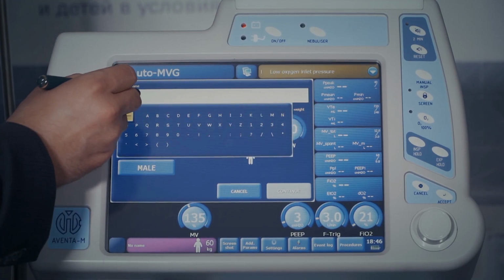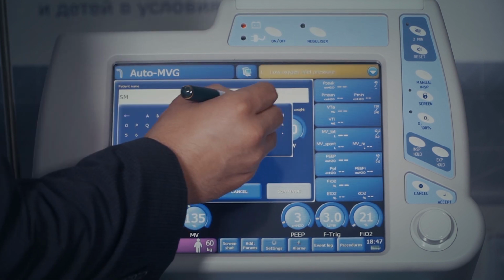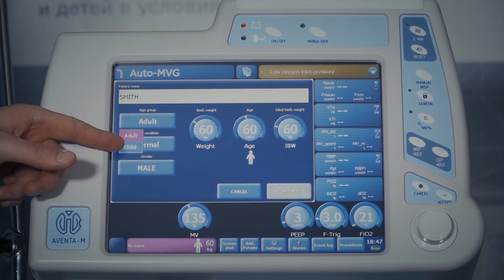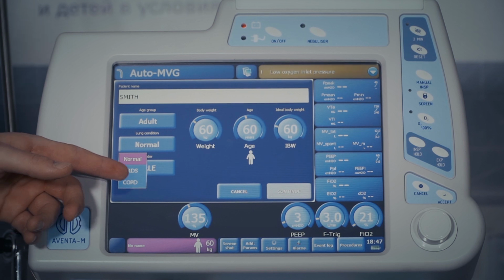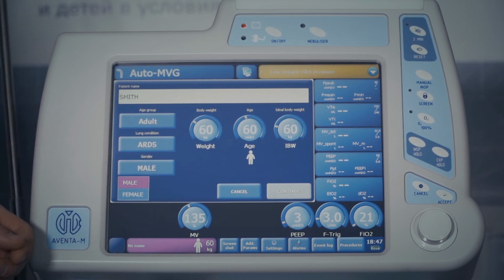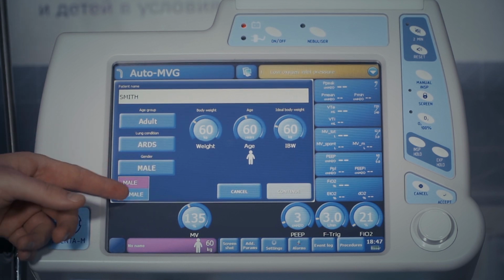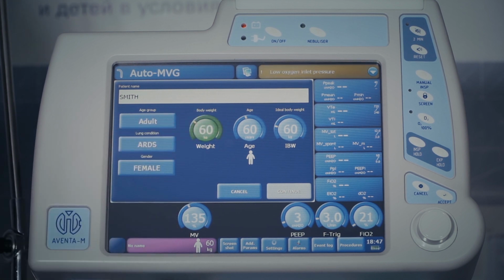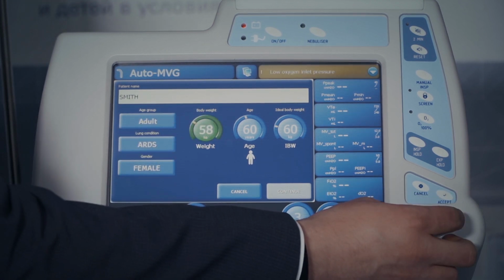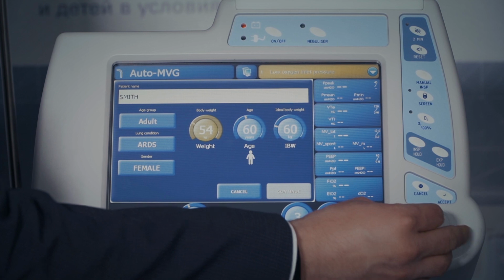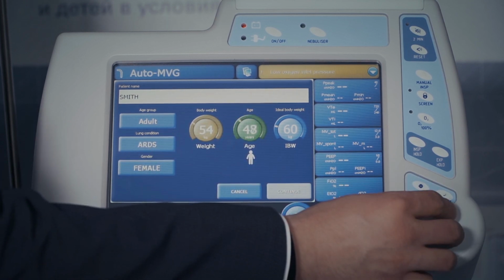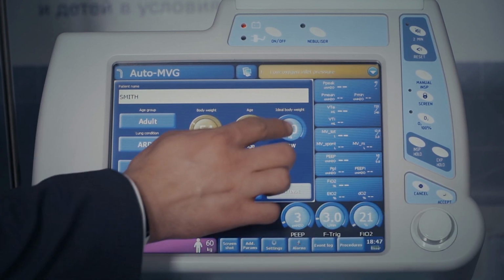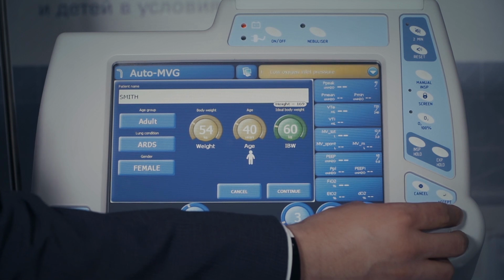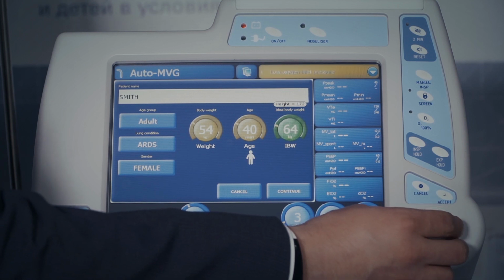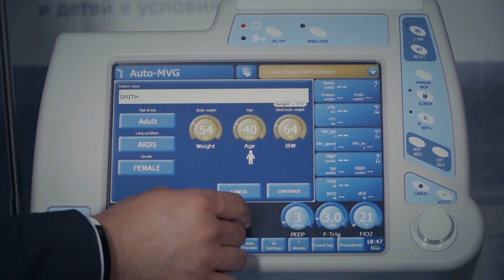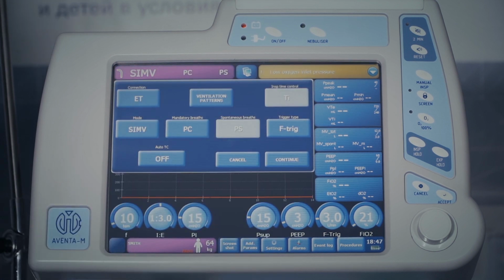A window for entering patient's information will be displayed on the screen. Patient name, age range, respiratory system condition specifics, sex shall be entered in this window. Using push-turn knob, select the patient's actual weight, age, and ideal body weight. The patient's ideal body weight may be determined based on the height displayed in a tooltip on the top during installation. Press button Continue and proceed to ventilation mode setting.